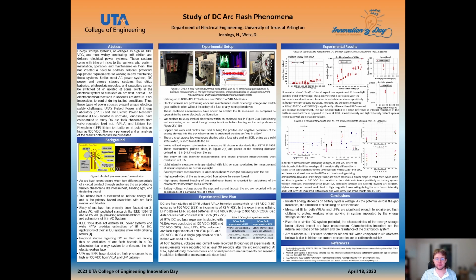Copper buswork and cables are used to bring the positive and negative potentials of the energy storage system into the box where an arc is initiated. The arc is set across two square electrodes shorted with a fuse wire initially, and an SCR, or silicon-controlled rectifier, is used as a solid-state switch to close or initiate an arc. We've utilized copper slug calorimeters painted black following the ASTM F1959 standard. This standard is used to characterize arc flash rating for clothing. These calorimeters are placed at a working distance of 18 inches away, found in standards like IEEE 1584 and NFPA 70E.